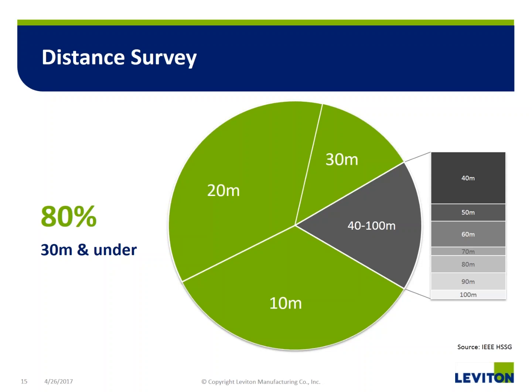IEEE settled on this 80% rule and said 30 meters is going to be just fine. If you think about it, in a middle-of-row topology where you can run the cable on both sides of your switch and server racks, that can support up to 60 cabinets. It's quite a big, quite a long length of cabling that you can support in the data center.